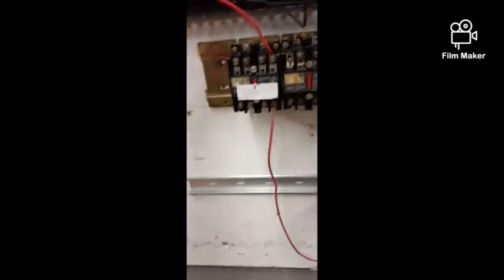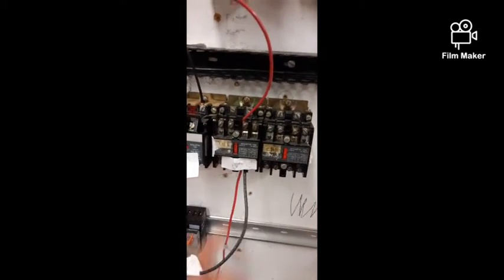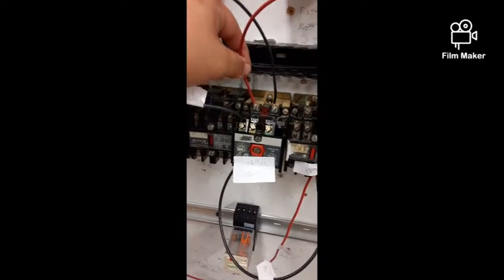control relay 3, down to your limit switch, back up to control relay 5. Then from control relay 5 it goes over to control relay 4 to energize this part. And then line 2 goes back up to X2 on the transformer.